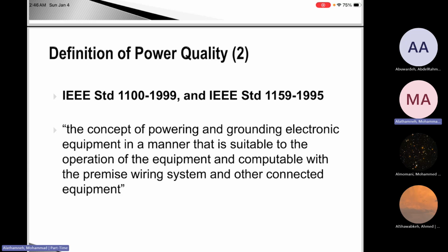But 1159, which dates from 1995, is heavily tied to monitoring and a consistent description of power quality phenomena. Basically, how we define events, how we measure them and how we talk about them, so engineers don't misunderstand each other. So IEEE is telling us power quality is not just a good voltage, it is also about proper grounding, wiring, compatibility and interaction among devices. It's not only about the voltage and a good waveform, but also the grounding, wiring, interactions, etc. That's why in real buildings you can have perfect utility voltage, but bad bonding or bad grounding creates noise and equipment problems. We will talk more about grounding in the next lecture, where there is a separate introduction to grounding and grounding problems.